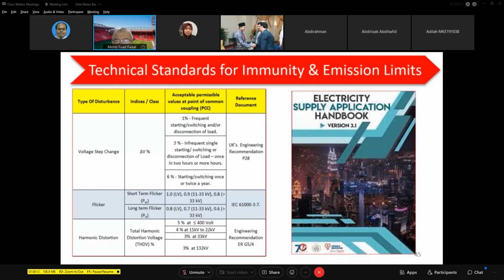Okay, based on these three references, to ensure compliance with these three regulatory requirements, TNB has published the Electricity Supply Application Handbook, or ESA, ESAH. The objective is to ensure the supply application process by consultants and contractors is done properly and safely. And for the PQ element inside this handbook, it defines the requirements for the customer.